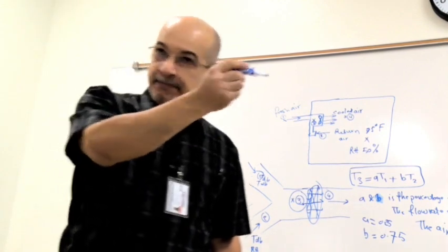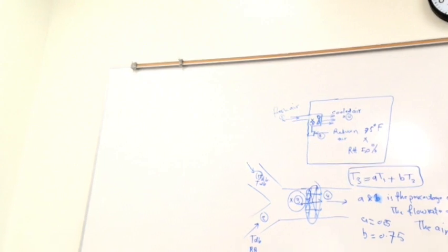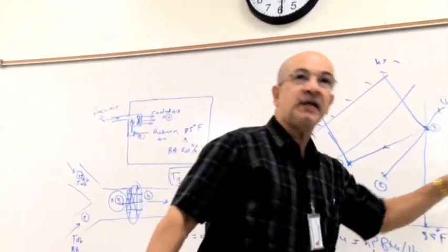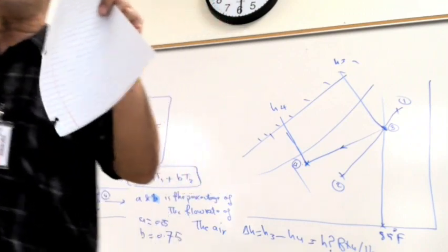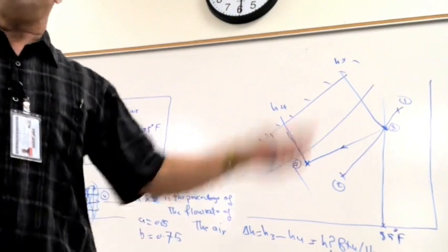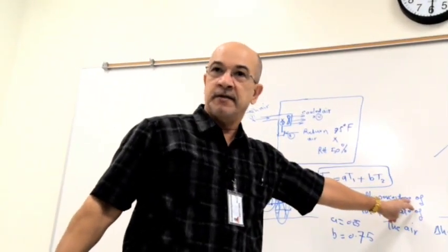Then we can convert it to tons. You know, every 1 refrigeration ton equals 12,000 BTU per hour. So we find it in BTU, divide by this, and we find the capacity in refrigeration tons. When you hear this equipment is 2 ton, 3 ton, 4 ton, they find it through this procedure. Understand? Okay, we'll do it step by step.